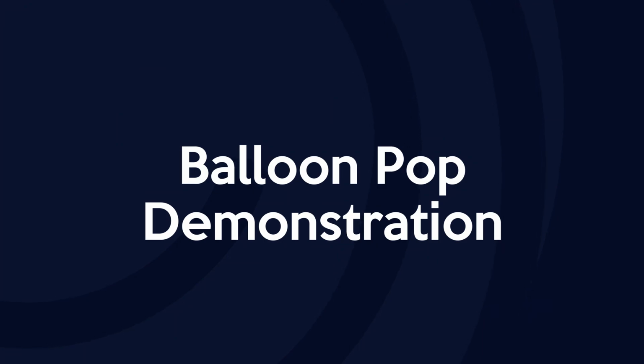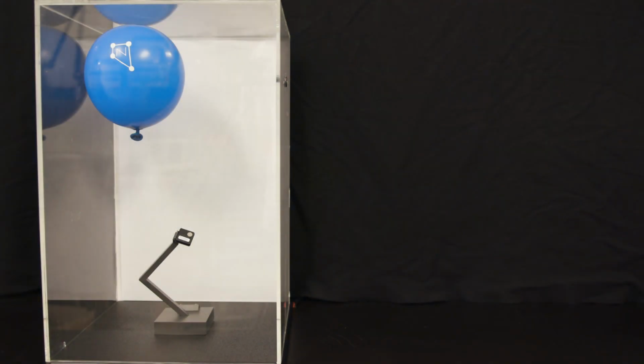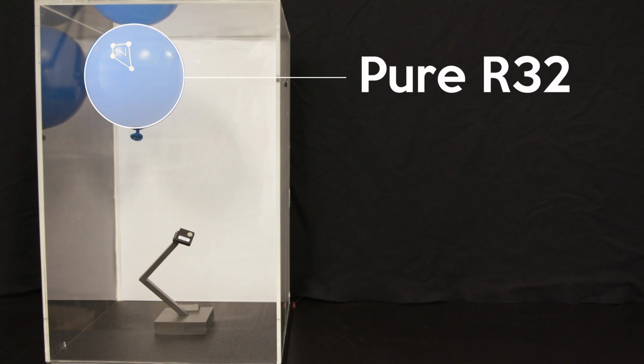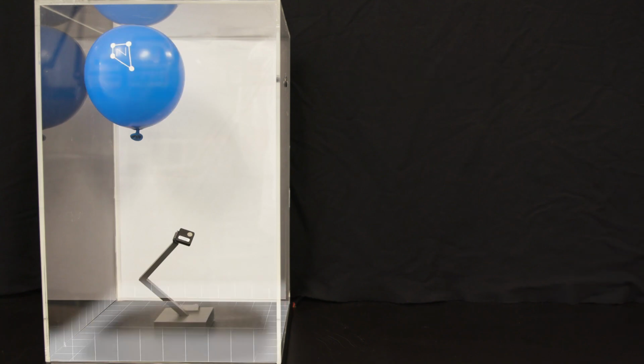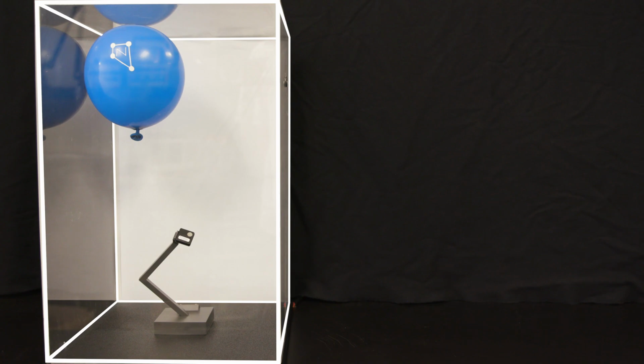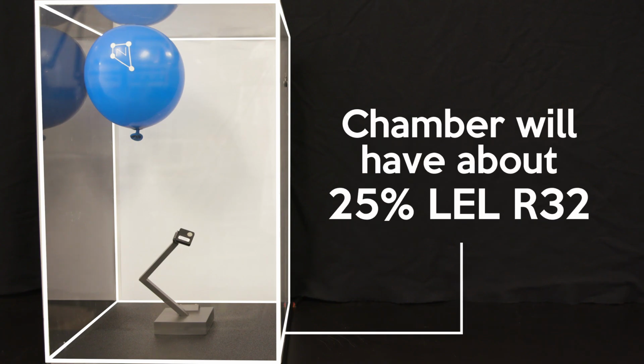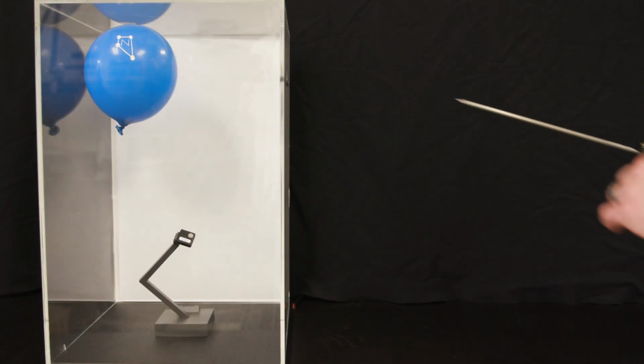So this is our balloon pop demo, and we like to use this to show the response time of the sensor. So what we have here is a balloon full of pure R32. Given the volume of this box here, once we pop that balloon, we'll have a volume of about 25% R32 in the chamber. And we've chosen 25% because of the ASHRAE and UL standards. Those kind of specify a maximum set point of about 25% LEL. So we'll go ahead and pop a balloon here.